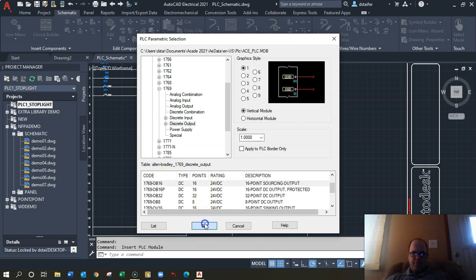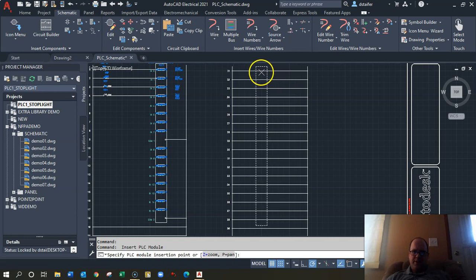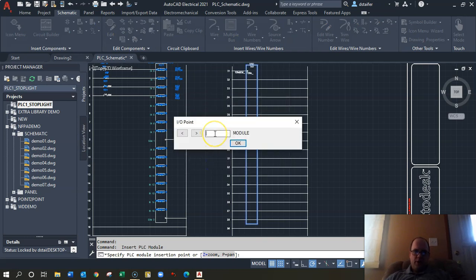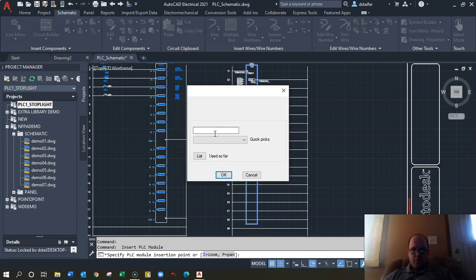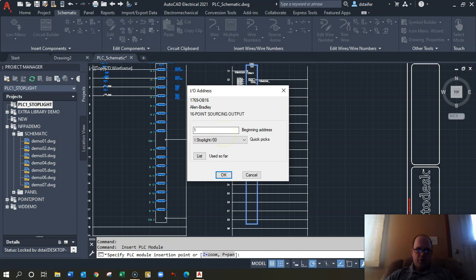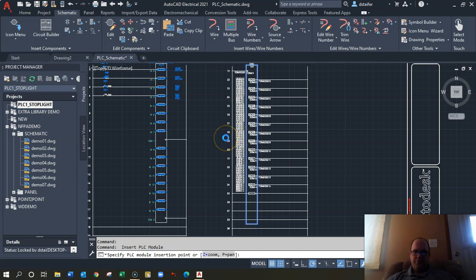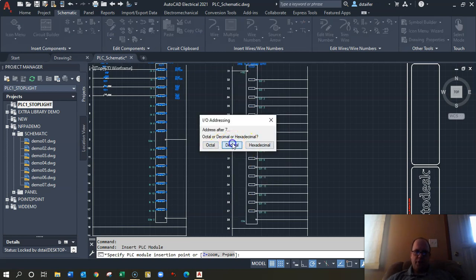Since this is an output card, nudge it a little more toward the beginning of the rung. Call it 'Stoplight' again because that's the processor. For the beginning address, I want slot 2, so make the beginning address 2. Select decimal format.